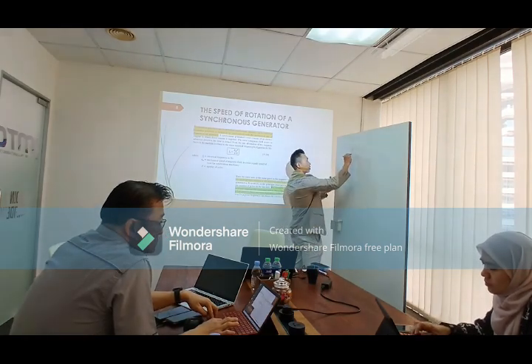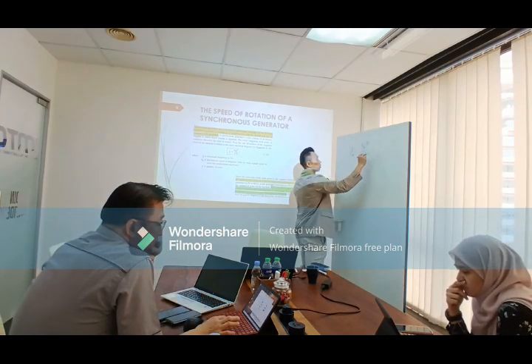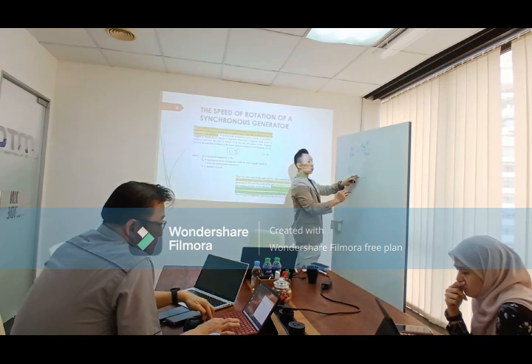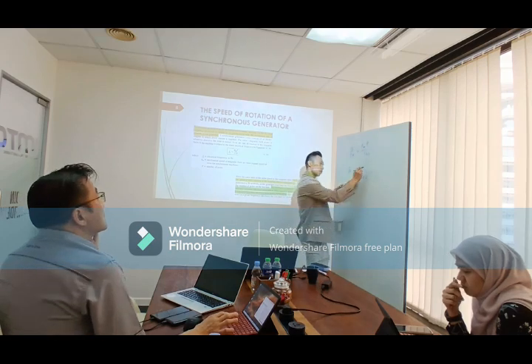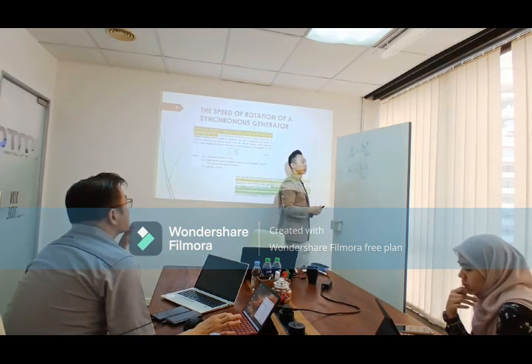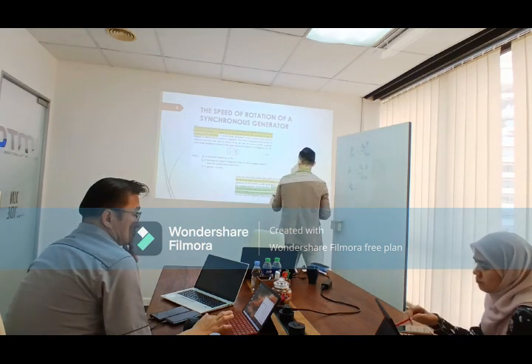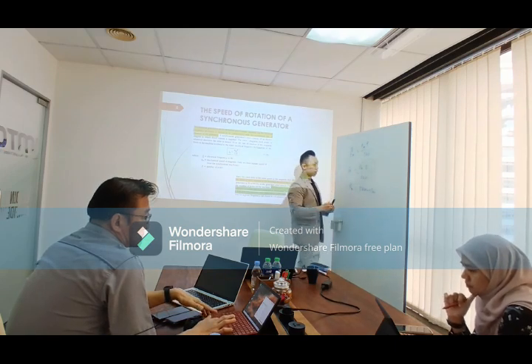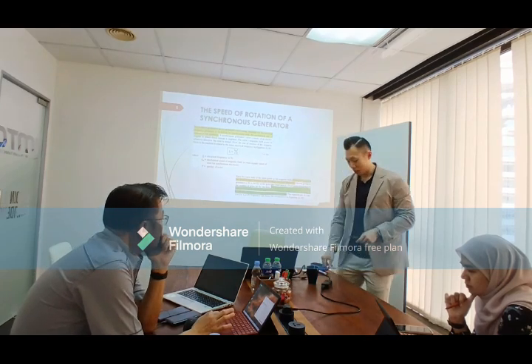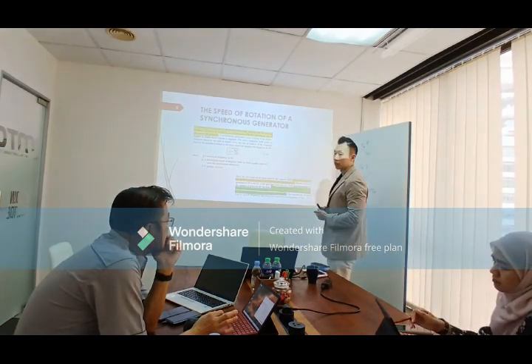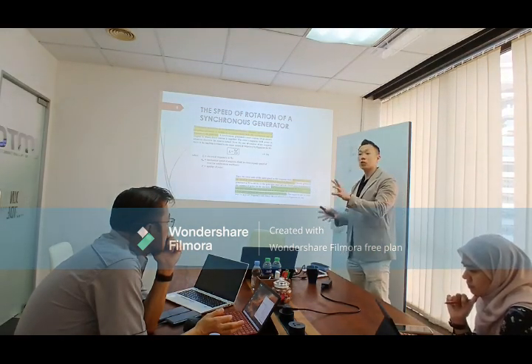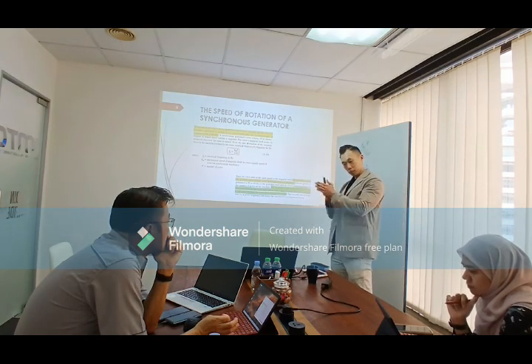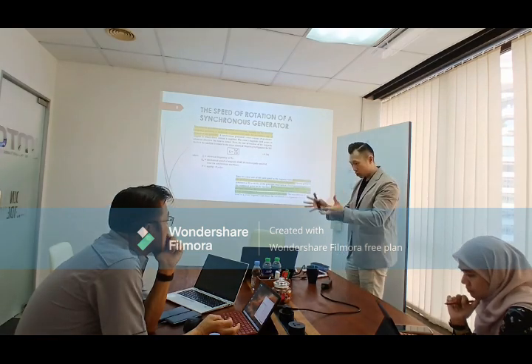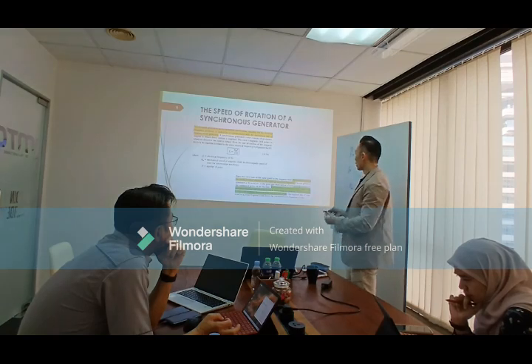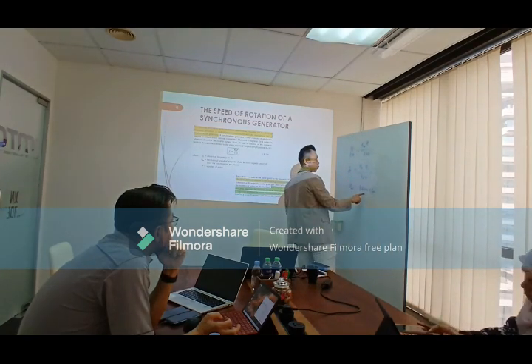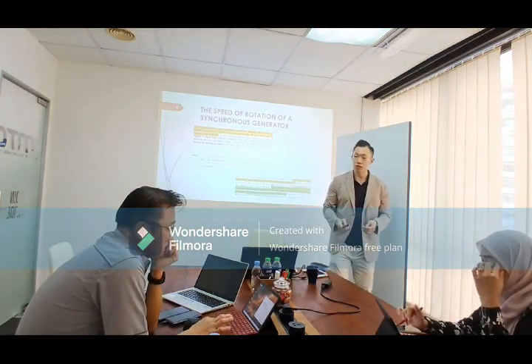So if I have this equation, and I want to achieve 60 Hz with only 2 poles - which is a non-practical configuration - the mechanical speed Nm works out to 3,600 revolutions per minute. That is very fast, and it's not healthy for the mechanical configuration of the rotor, because when the rotor turns too fast, the center of axis will be thrown out of position, causing bearing vibration first, and then the bearing will be dislocated. So instead of having 2 poles, we can increase the number of poles to reduce the revolutions of the rotor - that's what we can adjust.